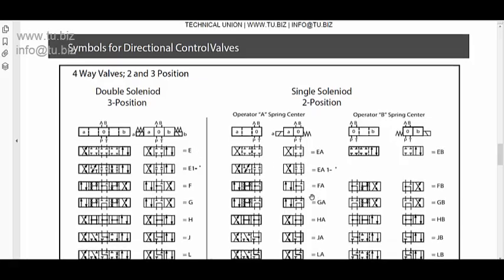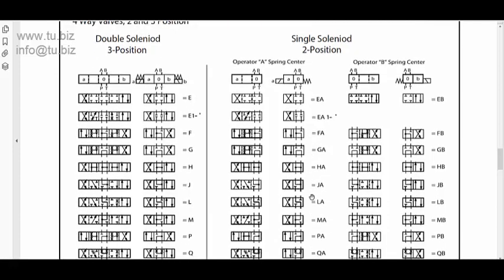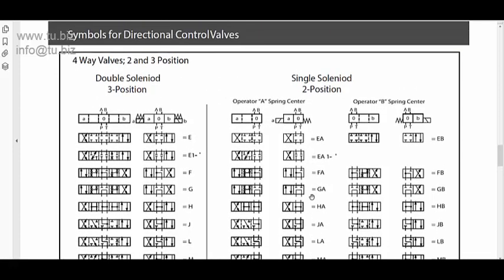If you have a two-position valve over here, you can have a spring return, or you can have a detent. A detent will maintain the position on the valve. So you energize it, and the valve goes to shift to pressure to A, and it'll stay to A. And you can de-energize the solenoid, and the valve will stay in the same position until you energize the other solenoid for the other position, and then it would give you the next position that you have.